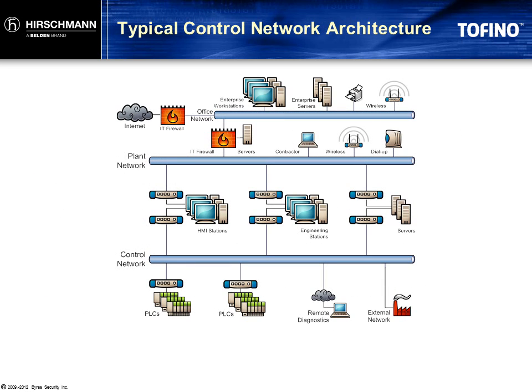Let's look at an example of how these problems can start and spread so quickly. This is a simplified diagram of a typical control system where the PLCs and sensors are connected to a control network that is isolated from the main plant network by dual-homed PCs. The plant network, in turn, is isolated from the enterprise network by a firewall. Finally, the enterprise network is isolated from the internet by another firewall.